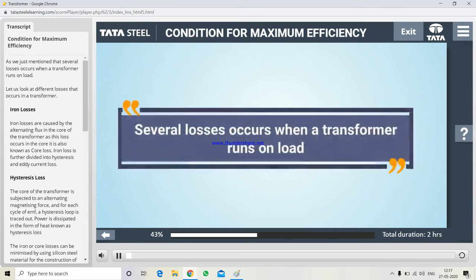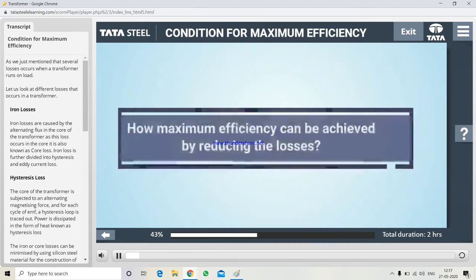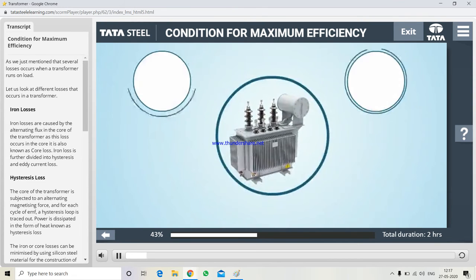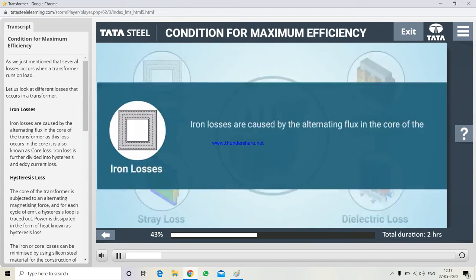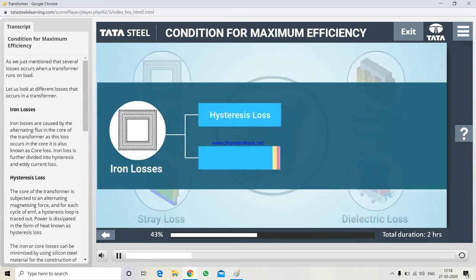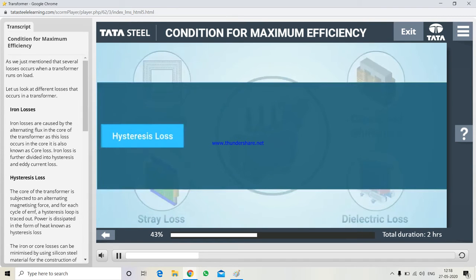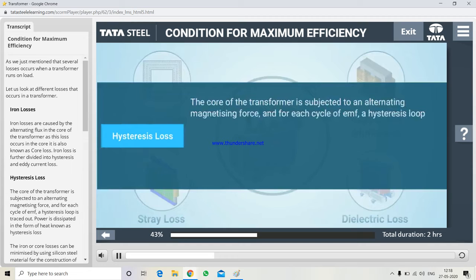As we just mentioned, several losses occur when a transformer runs on load. Let us look at the different losses that occur in a transformer. Iron losses. Iron losses are caused by the alternating flux in the core of the transformer. As this loss occurs in the core, it is known as core loss. Iron loss is further divided into hysteresis loss and eddy current loss. Hysteresis loss. The core of the transformer is subjected to an alternating magnetizing force, and for each cycle of EMF, a hysteresis loop is traced out. Power is dissipated in the form of heat, known as hysteresis loss.